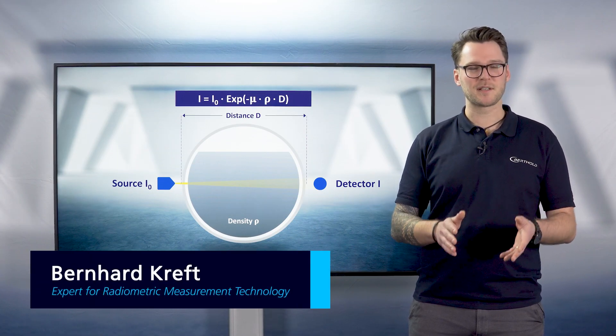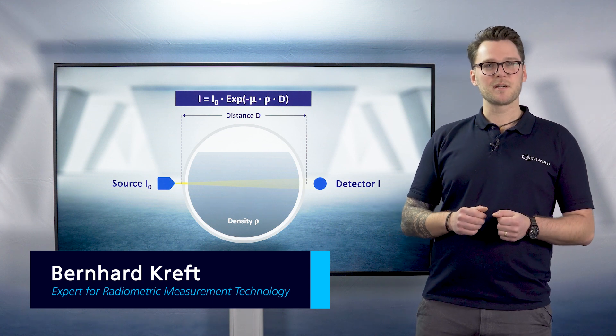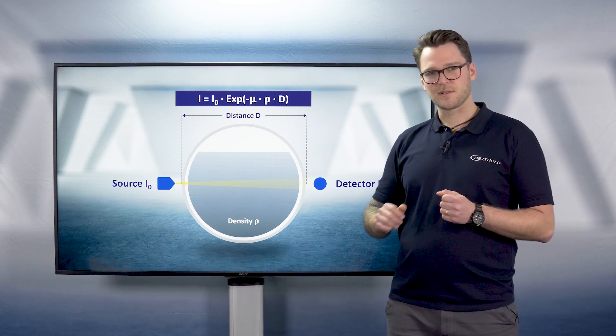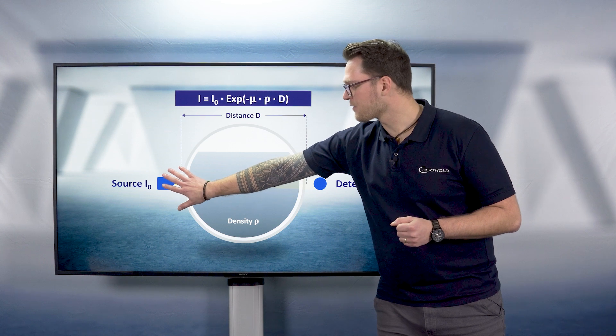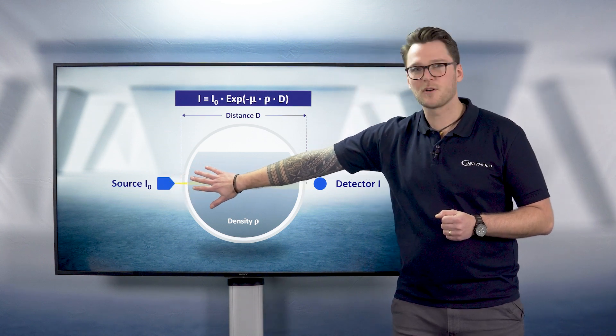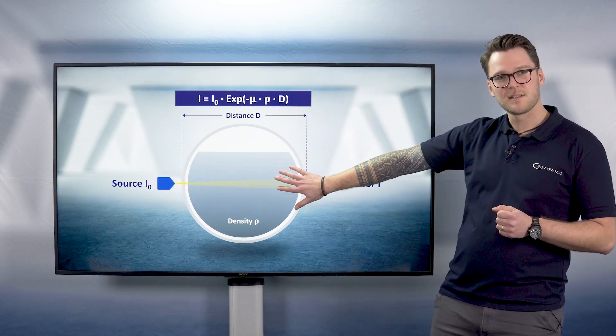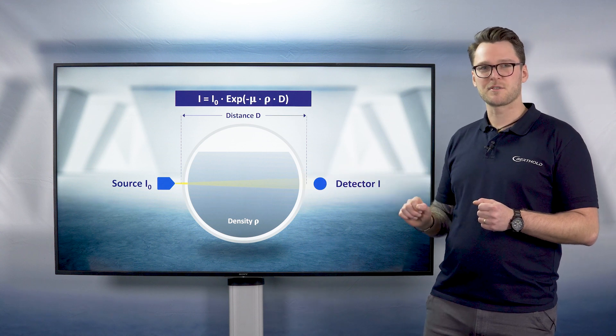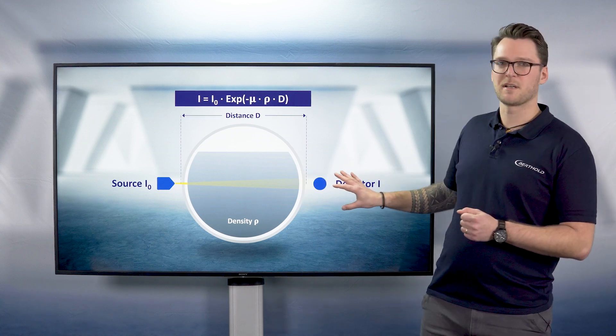Radiometric measurements are based on the sophisticated principle of attenuation. Radiation is generated on one side of the vessel and after being attenuated through the vessel walls and also its contents, the remaining radiation is measured by a detector on the other side.